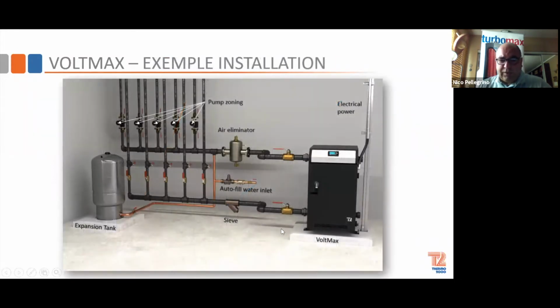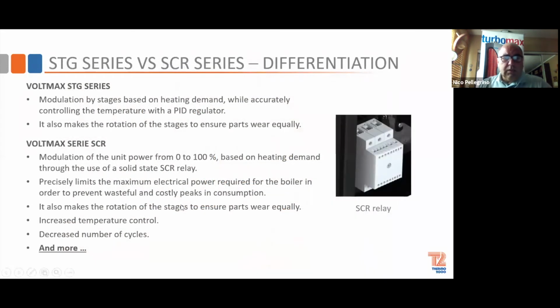So this is a nice little picture of an electric boiler, Voltmax, with some zone pumping. The 180 Voltmax comes in 2 types of controllers. We have the STG, which is more or less modulation by staging each element, and that's done with a PID regulator. And the good thing is it's not always the same stages, not always the same elements on at the time. They cycle and turn, so each element gets the same amount of runtime.